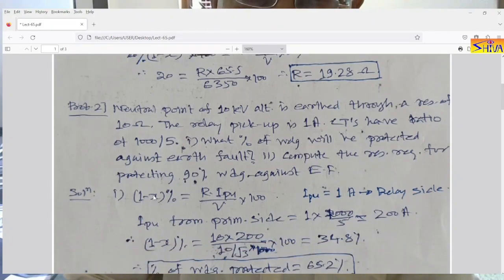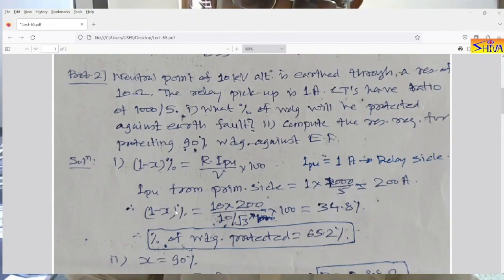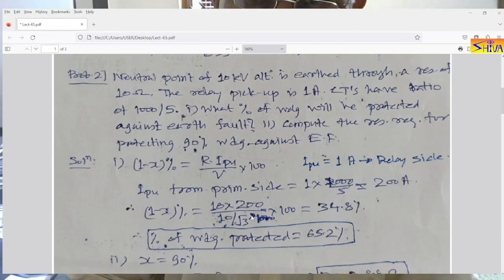Using the formula: percentage of winding unprotected = R × I_pickup / V × 100. The relay pickup is 1 ampere from the relay side, so from the primary side it is 1 × CT ratio (1000/5) = 200 amperes. The resistance R is 10 ohms and the voltage is 10 kV line, so phase voltage is 10,000 / root 3 volts. So the percentage of winding unprotected comes out to 34.8%.